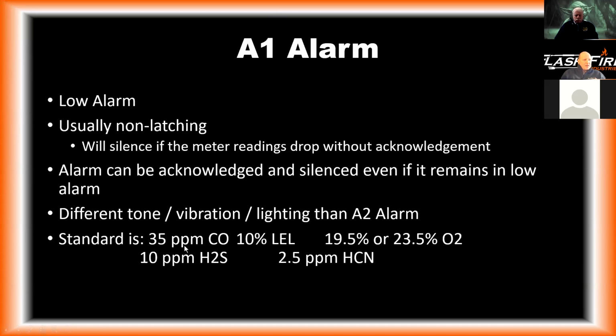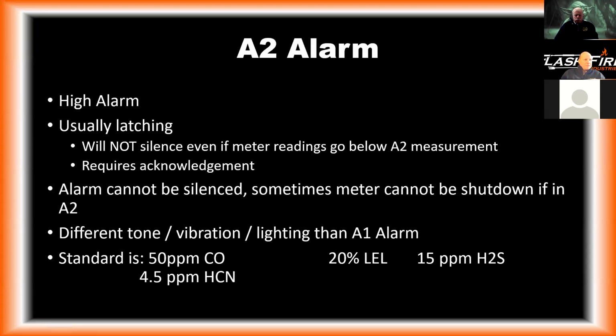The standard is 35 parts per million of CO, 10% LEL, anywhere outside of 19.5 or 23.5% of oxygen, 10 parts per million of hydrogen sulfide, 2.5 parts per million of HCN, hydrogen cyanide. Again, these numbers can be adjusted. So if you're in another department or something and it doesn't jive with this, that's not abnormal.